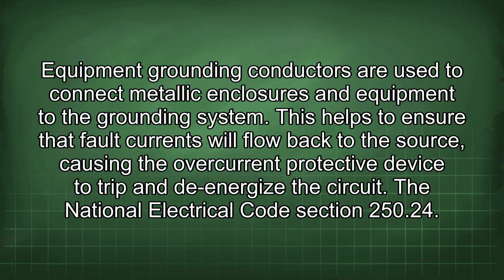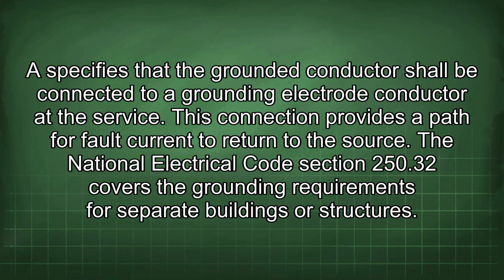Equipment grounding conductors are used to connect metallic enclosures and equipment to the grounding system. This helps to ensure that fault currents will flow back to the source, causing the overcurrent protective device to trip and de-energize the circuit. The National Electrical Code Section 250.24 specifies that the grounded conductor shall be connected to a grounding electrode conductor at the service. This connection provides a path for fault current to return to the source.